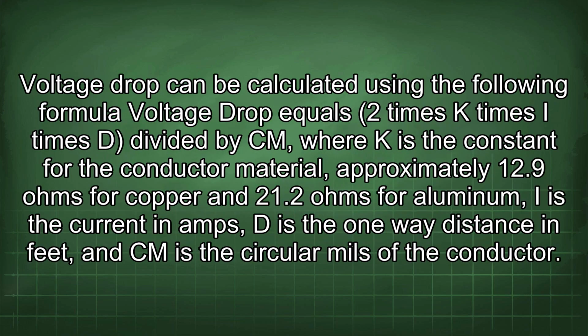Voltage drop can be calculated using the following formula: voltage drop equals 2 times K times I times D divided by Cm, where K is the constant for the conductor material, approximately 12.9 ohms for copper and 21.2 ohms for aluminum.